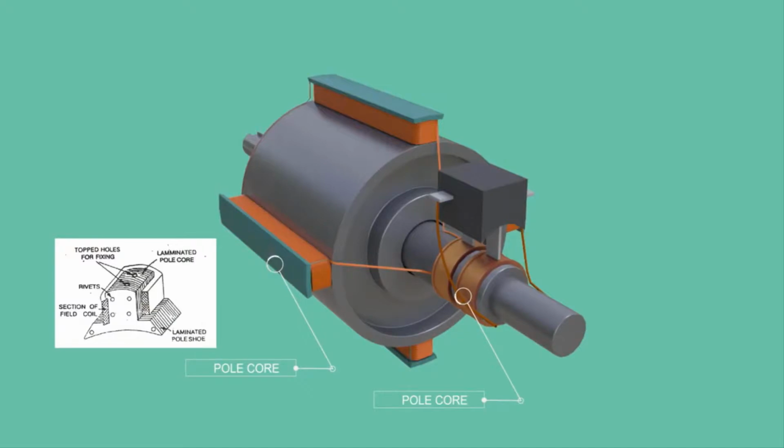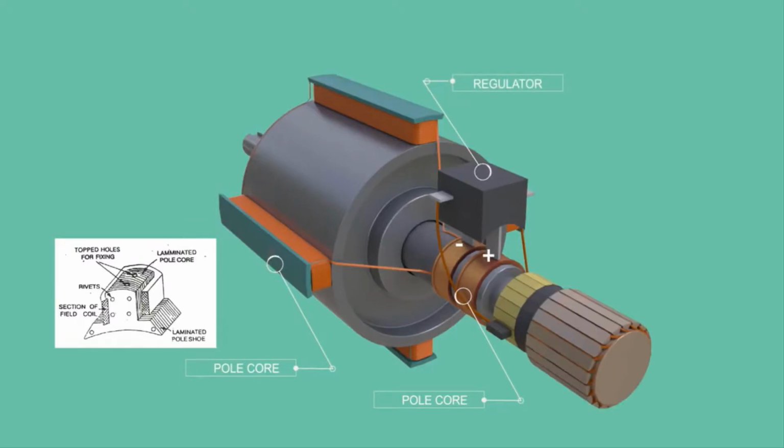If the rotating coil method were used, slip rings would have to be fitted along with the armature coils in order to collect electricity. But transferring such high voltage electricity with slip rings is rather impractical. It is quite possible to transfer low voltage DC excitation current with slip rings. This DC current is supplied either from an external source or from a small DC generator which is fitted on the same prime mover. Such alternators are called self-excited.